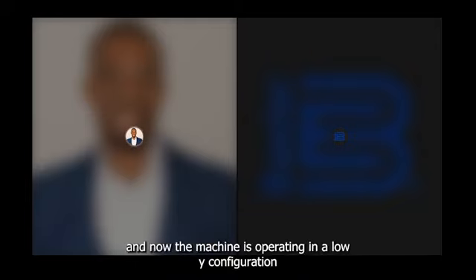Okay, it is just a multiplier that is used to determine by what factor mathematically the settings for voltage should be multiplied. For example, if you have a protection setting of pickup for overvoltage of 528 volts, and now the machine is operating in a low Y configuration, let's say it's operating at 208 volts, then you take that 208 and divide it by 480, which gives you a scale factor of 0.43. You also want your overvoltage protection to be multiplied by that same scale factor. That's your low line scale factor. Once that low line override status is given to the controller, it's going to apply that low line scale factor of 0.43 and adjust the overvoltage protection threshold by that much. So it's going to come down to somewhere above 208, maybe 240 or somewhere there.